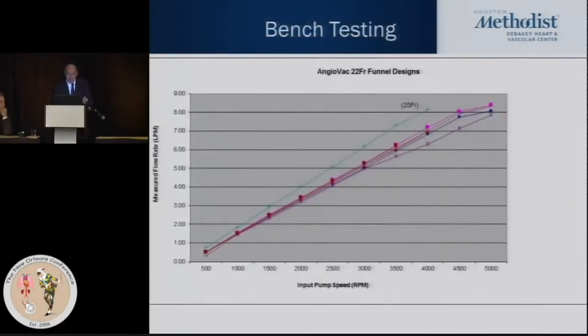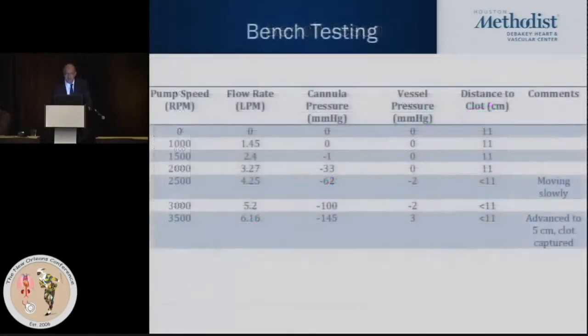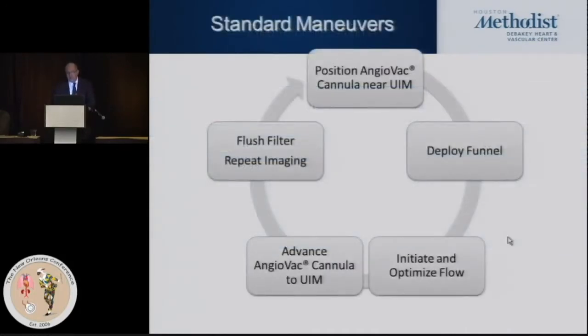They did bench testing and showed that at up to 5,000 RPM, you had a steady increase in the flow rate without any fall off for the 22 French design. They also showed that the cannula pressures became progressively more negative as you increase the flow. And at about 3,500 RPM, they found that when you got within 5 centimeters of the clot, there was enough suction to just suck the clot into it. So the maneuvers are fairly straightforward. You advance the cannula up to or near where the clot is, flush the filter and repeat imaging to check your position, deploy the funnel, and then initiate an optimized flow.